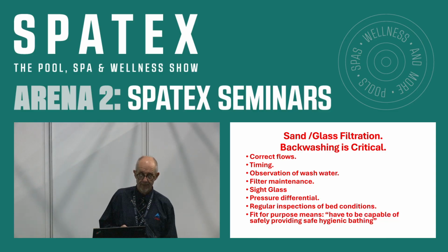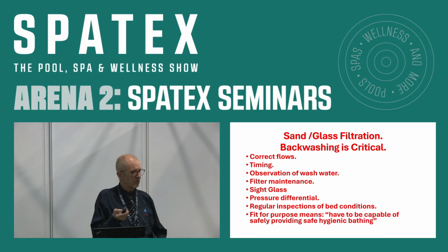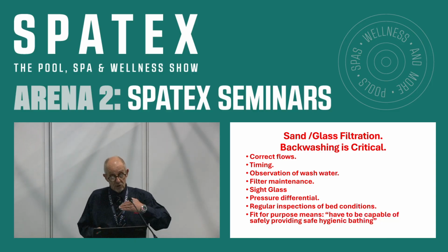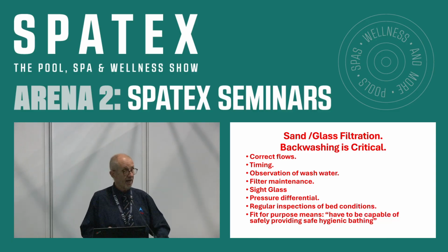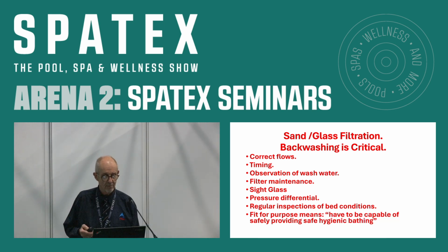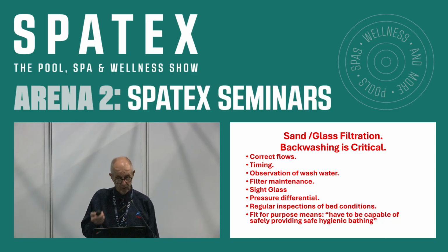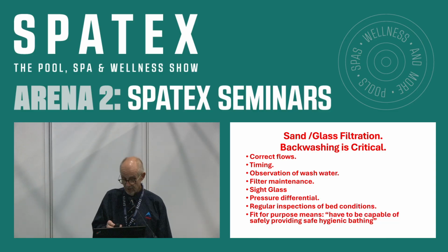Sand glass filtration. Now, glass has come in over the past 10 years, perhaps a bit longer than that. You've got to have the correct flows through the filter, okay? Timing is absolutely essential. Observation of the wash water for backwashing, filter maintenance, checking, a glass panel on the side is invaluable. And I've got some very good slides of that. Sight glass for backwashing, some don't have them. Pressure differential should be monitored closely. Regular inspections of bed conditions.